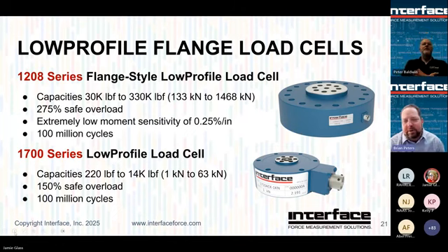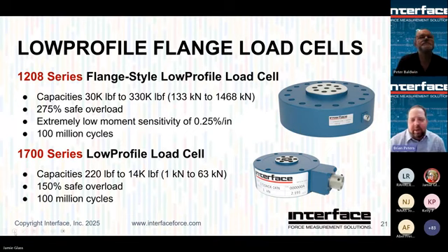There's other actuator types out there that have specific bolt patterns, or if you're at a really high capacity, it's a lot more convenient to not have to deal with a single large thread, which a big LP with a base on it becomes not the lightest sensor, and from an assembly standpoint, these are a great option. But they're also fatigue rated. Not a lot of people know that. Wide range of capacities, good safe overload, and also less sensitive to off-axis loads than, say, a standard 1200 series, and again, 100 million fully reverse cycles.